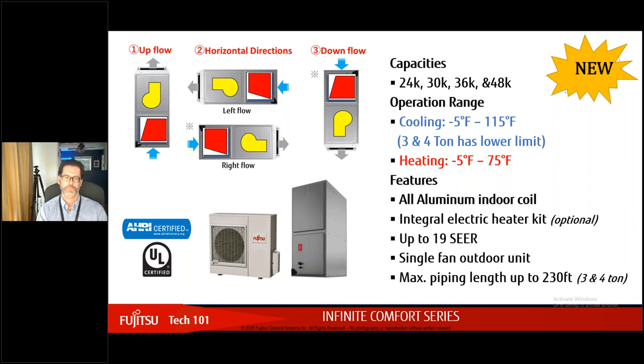Typically with the smaller ones, again, here I'm going to cookie cut something. Typically with the smaller ones, it's about 66 feet. So you can't go 80 feet, but that's where the customer wants the outdoor unit. And that's when things start to snowball and downward spiral, and not in a good scenario. So we have to understand what model we are positioning ourselves to be selling. What are the capacities or the maximums or the minimums on the line sets?